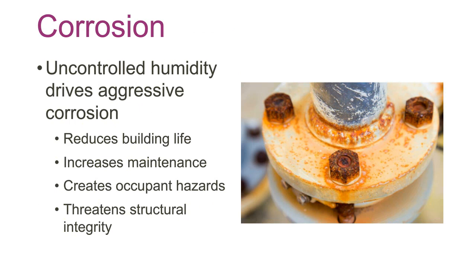Because of the chemicals that treat the pool water and keep it healthy, they migrate out, and you have corrosion. The humidity, uncontrolled humidity, is going to drive aggressive corrosion as well as the chemicals. So if you keep the humidity under control, 60% or below all year, you're going to increase the life of your facility. And if you do not do that, you can very much create big problems for corrosion and growth of organisms that you don't want to grow.